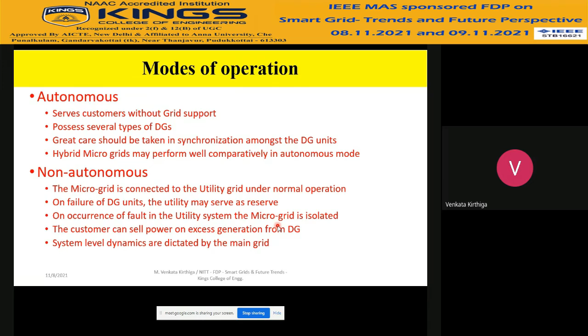Whereas in non-autonomous mode, you are physically connected to the grid, but if it's possible to generate more, you can keep generating so that the grid becomes a backup unit. In this case, the connecting transformer will have a very good life because you are reducing the load upon it. Normally transformers are continuously in operation, so when you connect through the transformer and operate in non-autonomous mode while still generating as much as possible, the life of the distribution substation transformer will improve. That is the major difference; otherwise you always have to take care of the other architecture-based issues we have discussed.